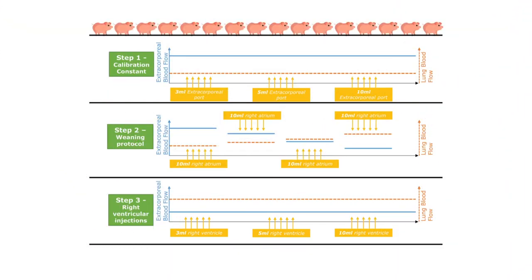The researchers tested their hypothesis in 16 pigs that were centrally cannulated for veno-arterial ECMO. First calibration constants were calculated with injections of 3, 5, and 10 milliliters of cold saline into the ECMO circuit at a flow rate of 4 liters per minute.